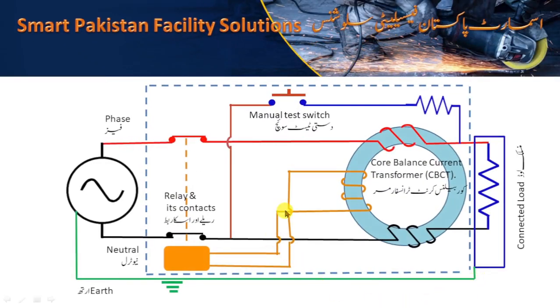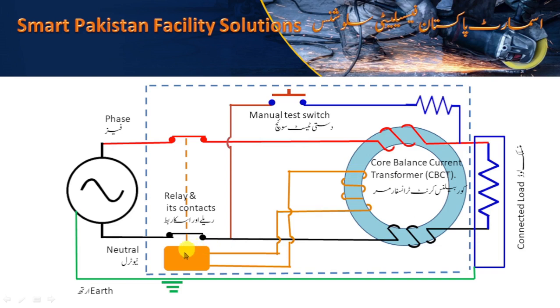Let us see its construction. This is the basic circuit diagram of ELCB. This dotted portion is the part of ELCB. It consists of two main components: the current transformer and the circuit breaker relay. This is known as the Core Balance Current Transformer, whose abbreviation is CBCT. It has two primary windings and one residual winding, which operates this relay in case of a fault in the load.